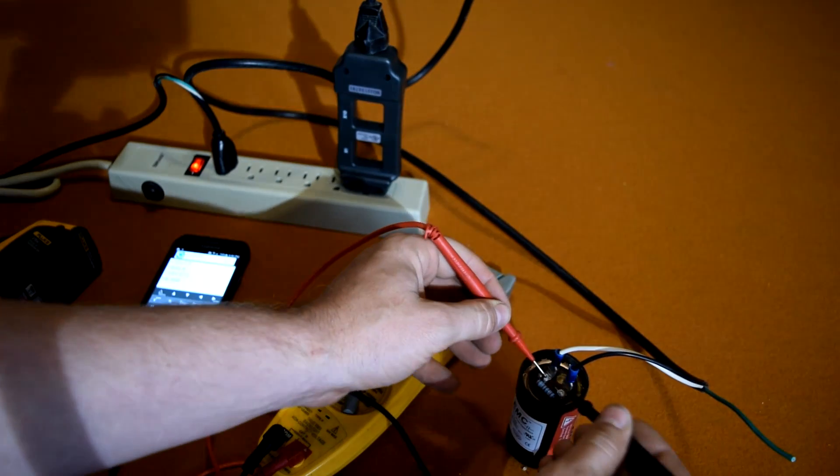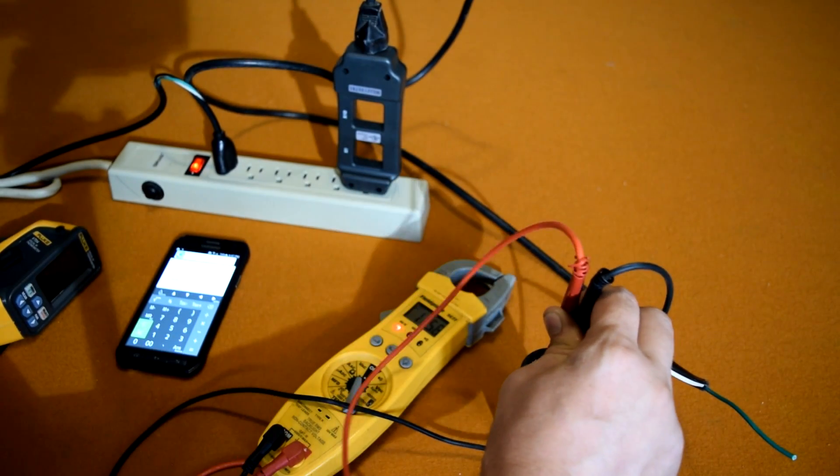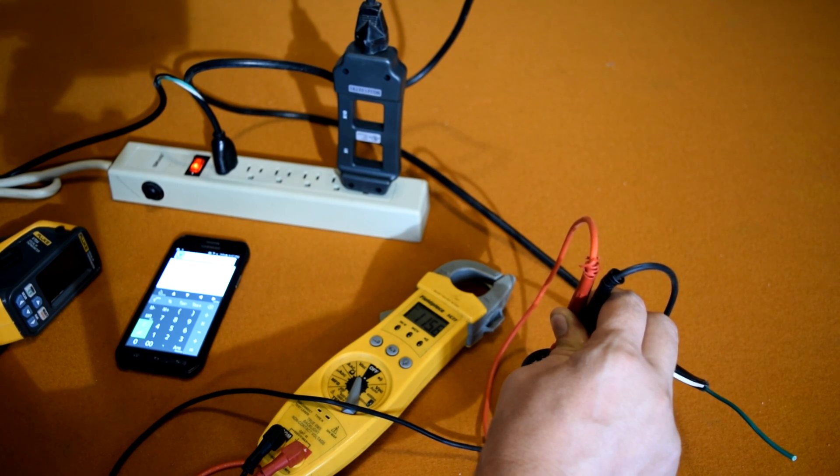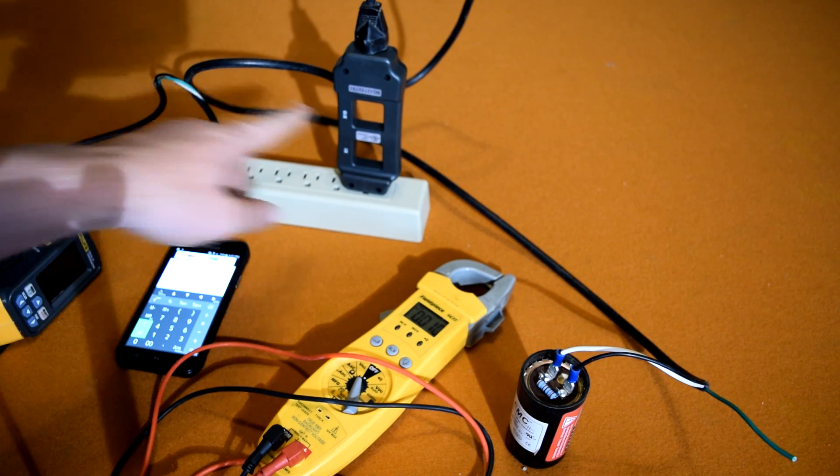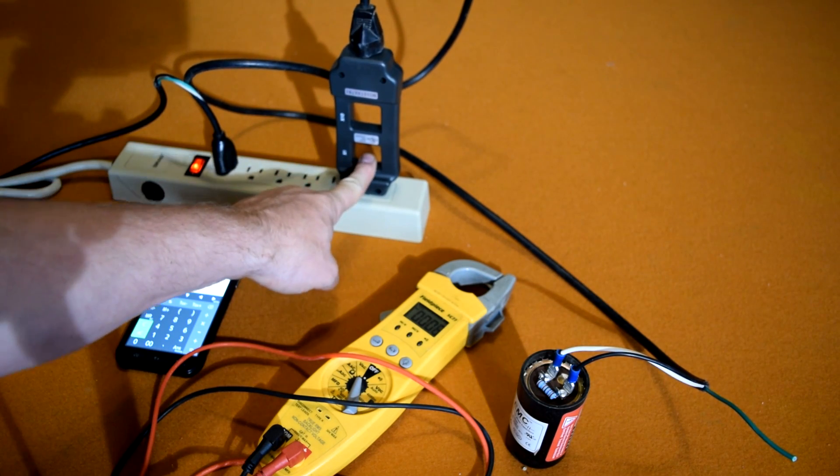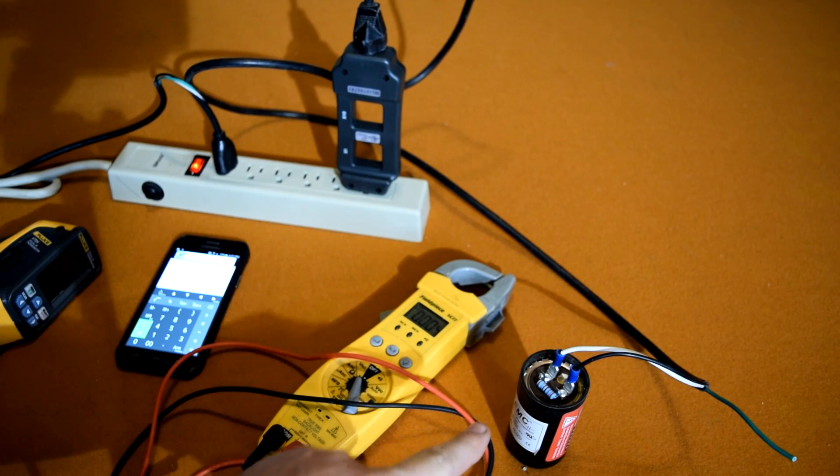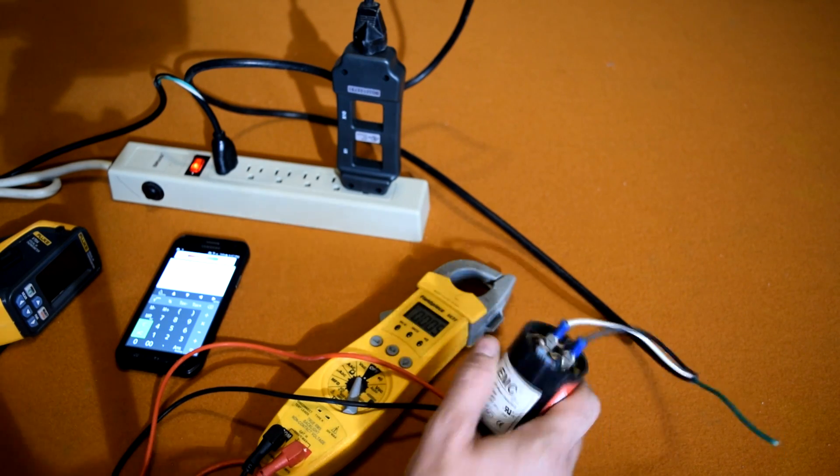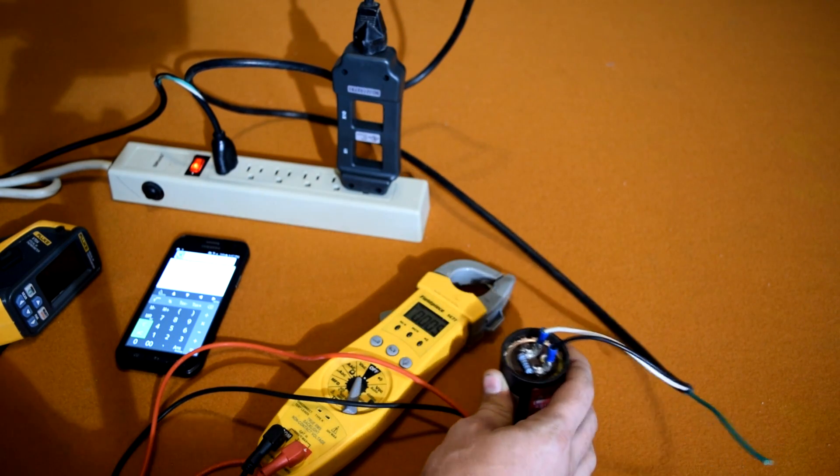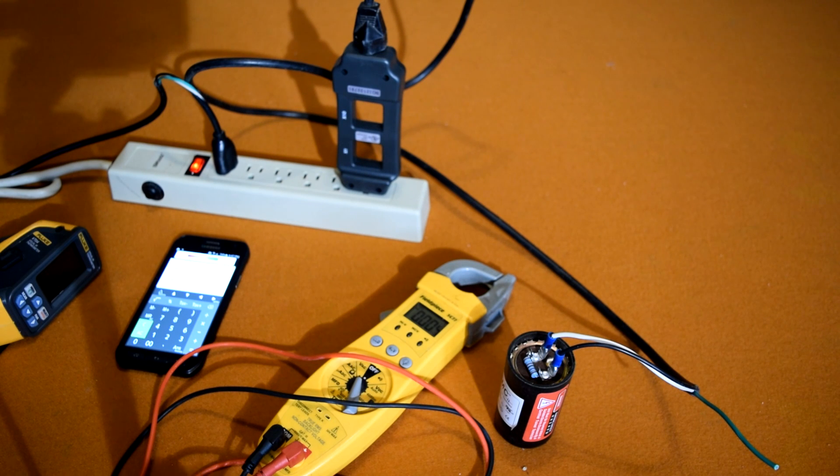Adding a capacitor to a circuit like this is not only dangerous because it gets hot and could explode depending on how you put it in. If you put it in a metal box and ground the box, it's probably fine. But if you don't ground the box and this thing gets hot enough, it's going to explode because it's under continuous load and never tries to shut down. These capacitors are supposed to be inline to a start circuit to a motor.